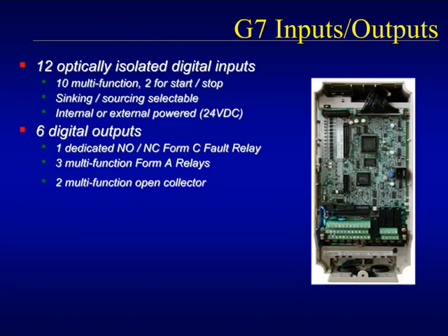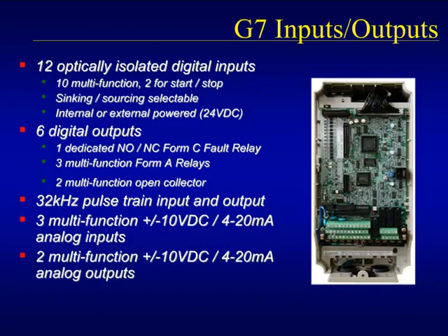The G7 offers the functionality to accept or source a pulse train. This makes the G7 simple to integrate with PLC pulse train cards and makes master-slave applications extremely simple and cost-effective. Multiple analog inputs and outputs provide further drive control possibilities. Both the analog inputs and analog outputs offer both 0 to 10 volts or 4 to 20 milliamp solutions.